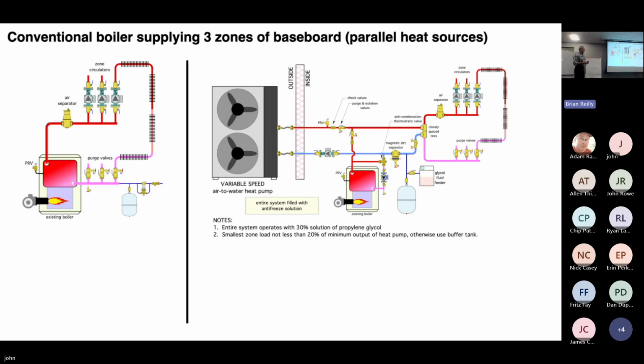I feel it's important that if you have a component, be it an air to water heat pump or a boiler, there's a possibility you might have to remove that at some point for service or replacement. So you should be able to close off valving so that, for example, if I had to remove the heat pump, I don't have to drain the entire system. I can keep the boiler operating, keep heat in the building. If I had to remove it, or maybe I have to replace this hose here, I could shut off that ball valve. I could shut off the ball valve inside the isolation flange.